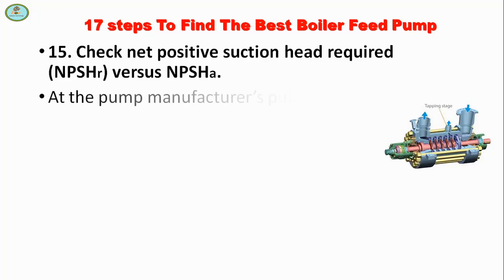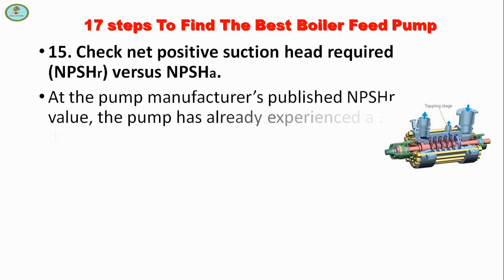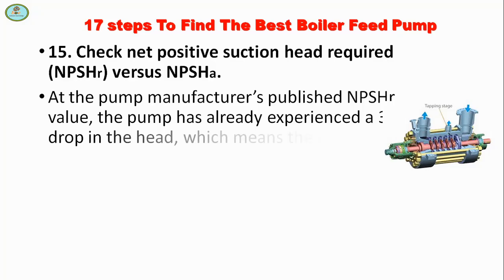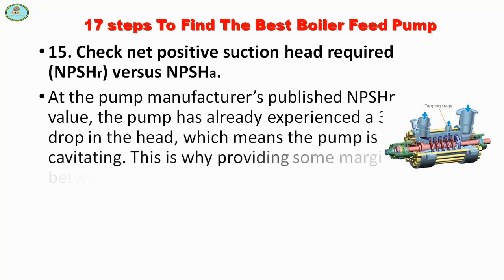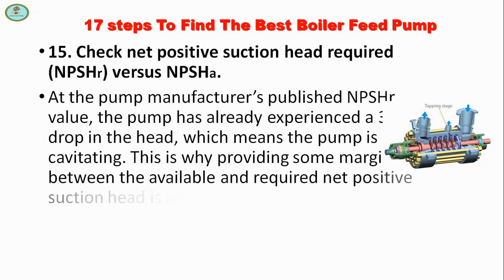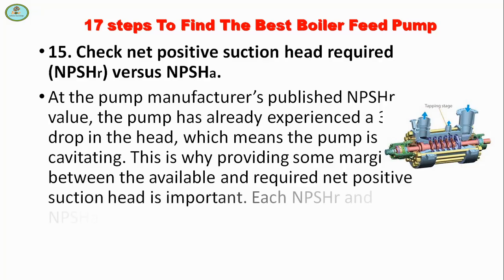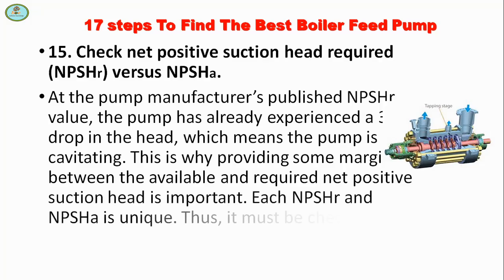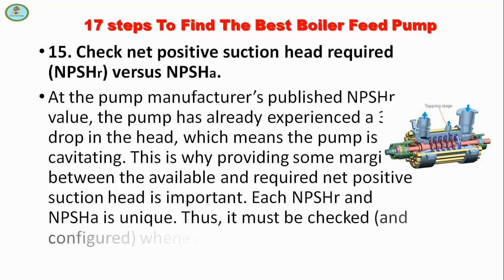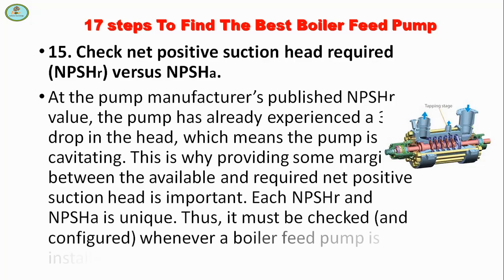At the pump manufacturer's published NPSHR value, the pump has already experienced a drop in the head, which means the pump is cavitating. This is why providing some margin between the available and required net positive suction head is important. Each NPSHR and NPSHA is unique, thus it must be checked and configured whenever a boiler feed pump is installed.